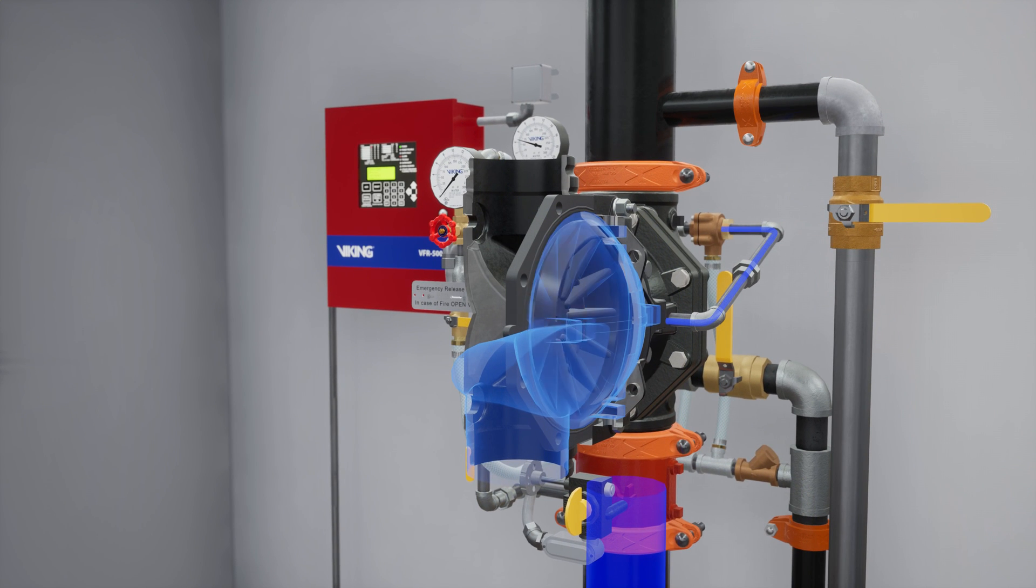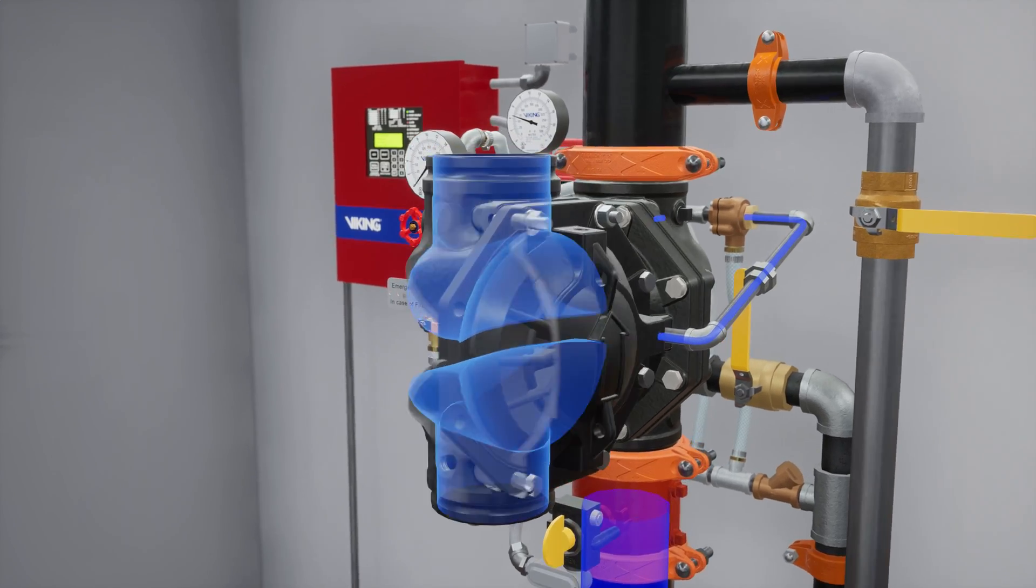Once water pressure is released from the priming chamber, the clapper is forced open by the supply water pressure from the inlet chamber, filling the valve body and connected trim with water.